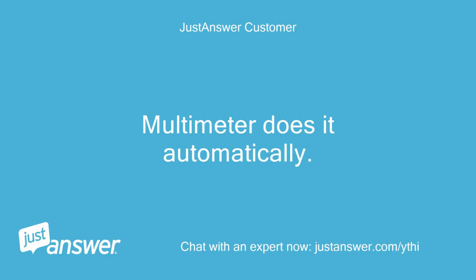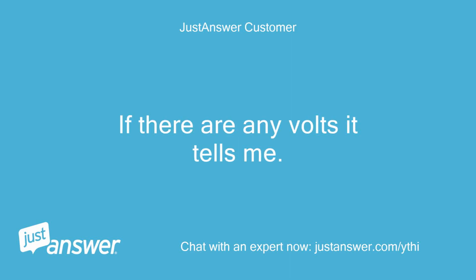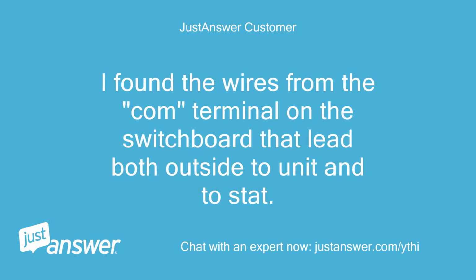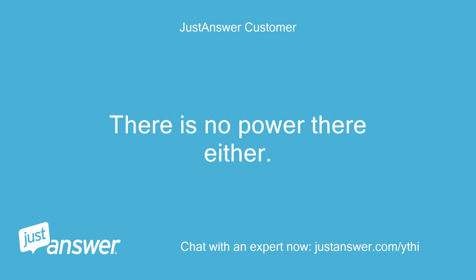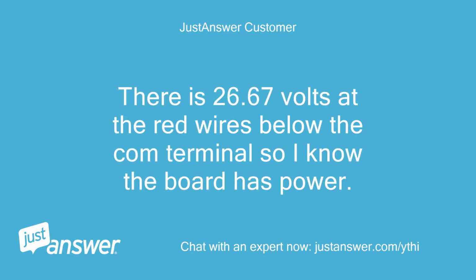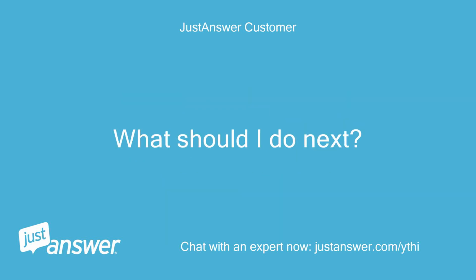Multimeter does it automatically. If there are any volts, it tells me. I found the wires from the COM terminal on the switchboard that lead both outside to unit and to stat. There is no power there either. There is 26.67 volts of the red wires below the COM terminal, so I know the board has power. What should I do next?